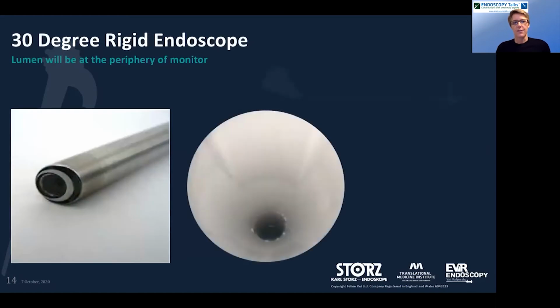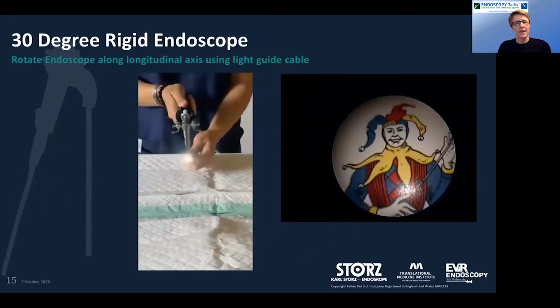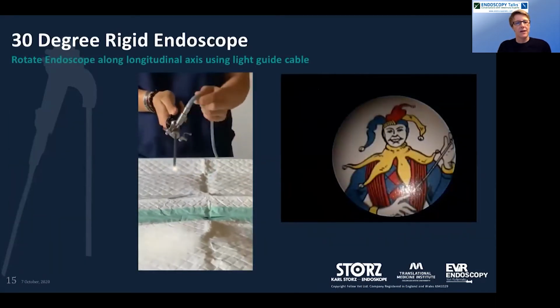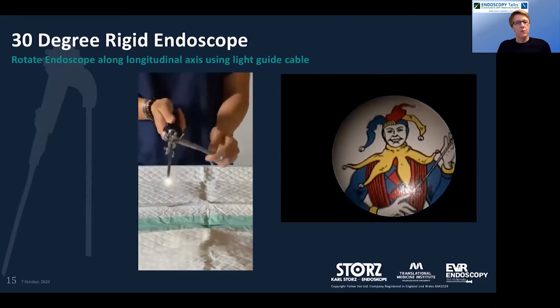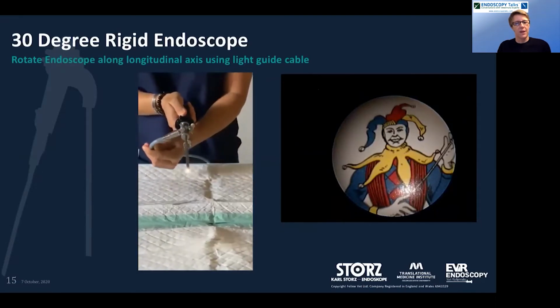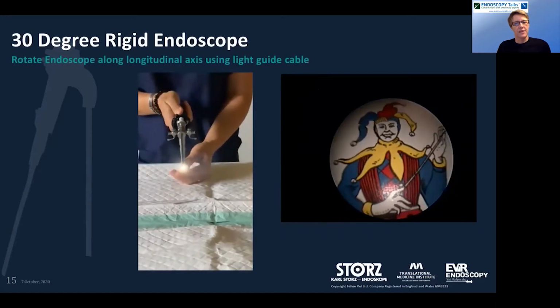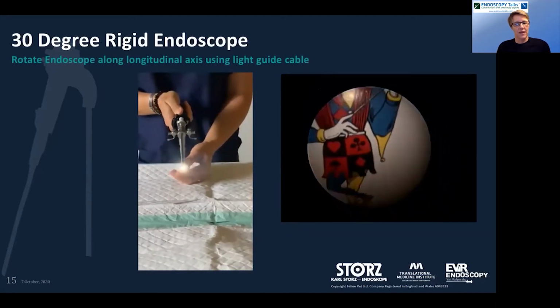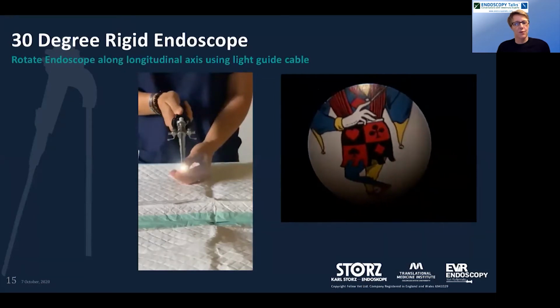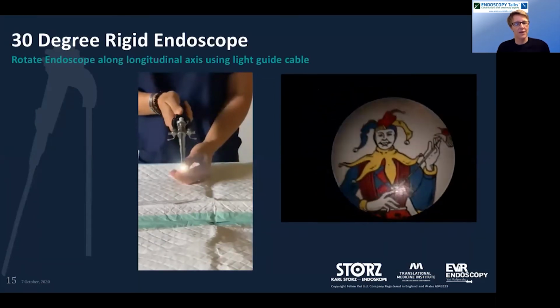So when we're using a 30-degree oblique telescope, typically when you're looking at the monitor, the lumen will either be in the periphery. So it will either be on the bottom, the top, or the sides, really depending on the position of where your light guide cable is. So again, if you rotate the light guide cable around, that will give you the peripheral image. And as you can see with the Joker, as you're moving the light guide cable around, see how it definitely expands your field of view just by having that bevel bend.